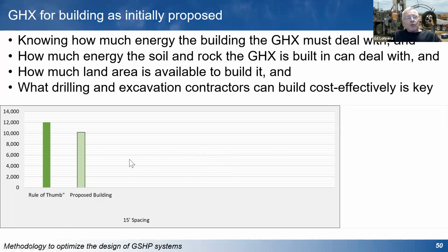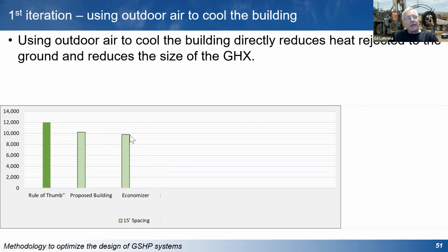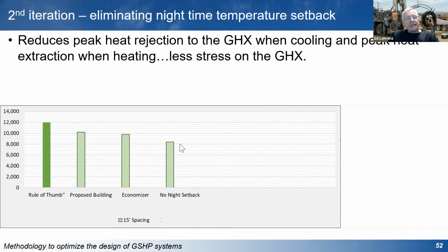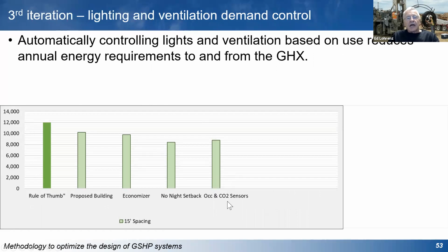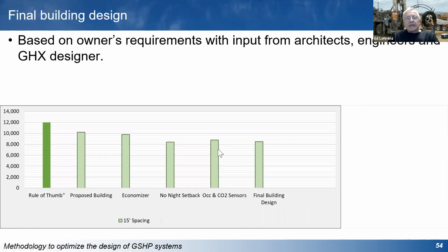Based on the rules of thumb, the proposed building would require about 10,000 feet of drilling. So we reduced the amount of drilling that's needed, even using the first energy model, by about 2,000 feet. That's a fair chunk of change that helps make these things a bit more cost effective. Next step, we looked at what happens if we add an outdoor air economizer or eliminate the night setback on the system. The night setback was actually surprising, how much difference that made. Occupancy and CO2 sensors are roughly the same, a slight increase in the size of the ground heat exchanger, amount of drilling that's needed. And then the final building design came in right around just over 8,000 feet of drilling, based on what the owner requires, and on input from architects, engineers, and the ground heat exchanger designer.